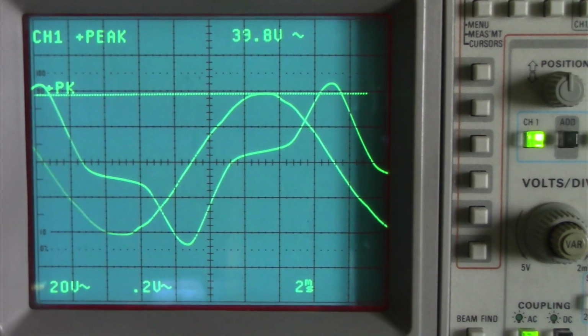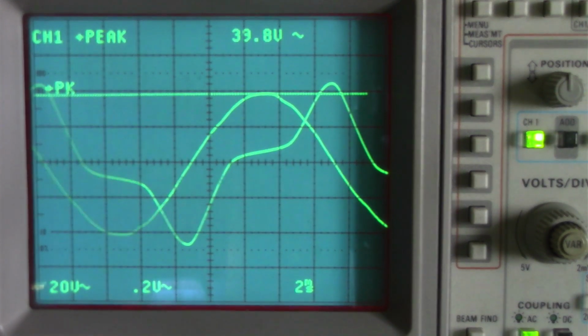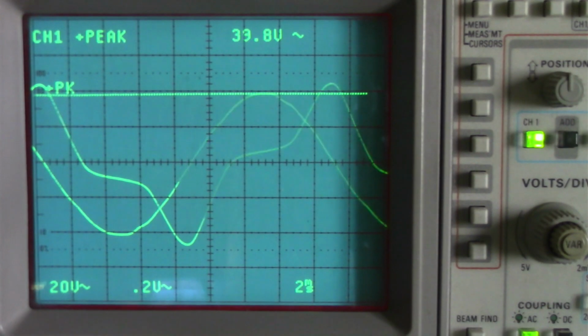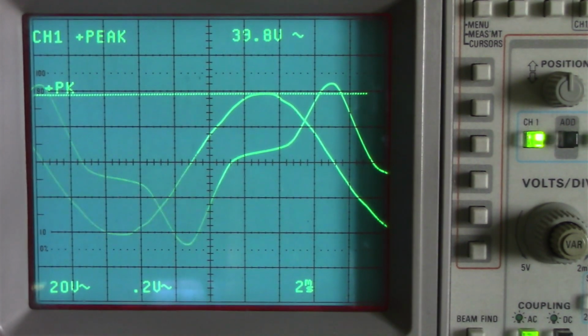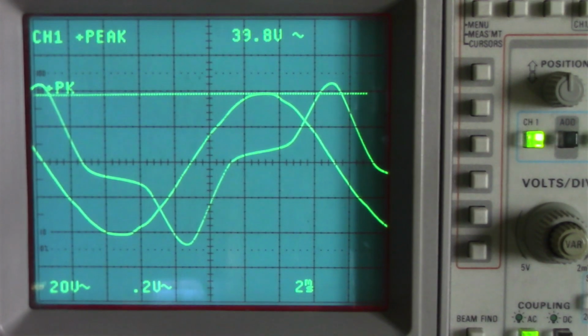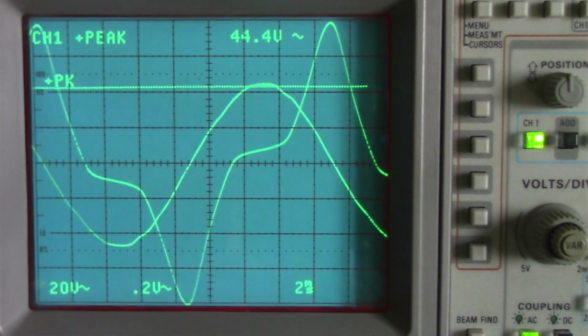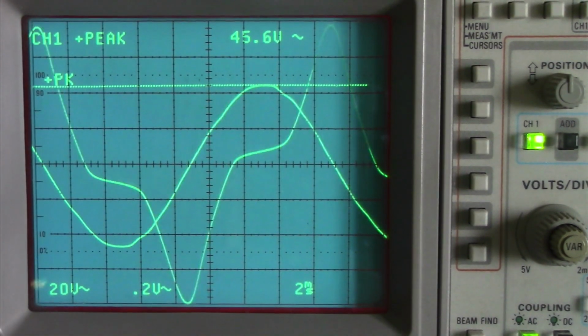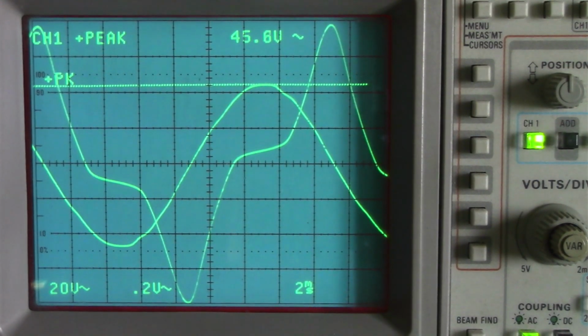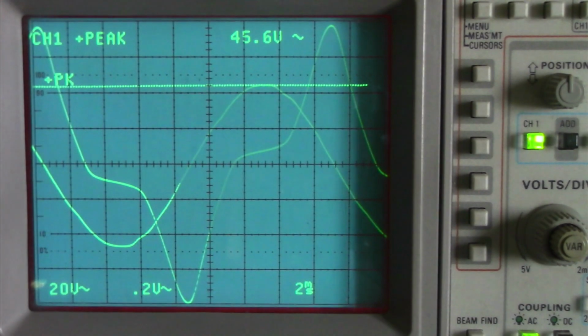We're now at an input of about 40 volts peak, and I would argue that there was a mostly linear relationship, right? The voltage went up and the current went up roughly the corresponding amount, but watch this. You can see that a very small change in voltage has now resulted in a very large change in current, and that's happening because that core is saturating.